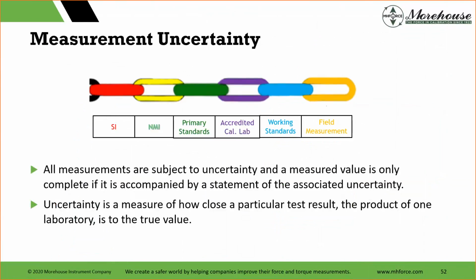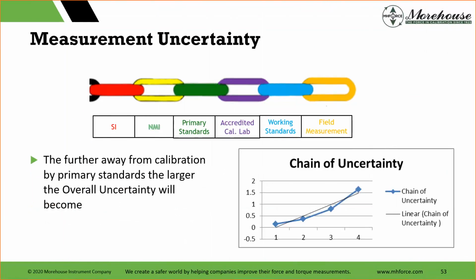Measurement uncertainty. All measurements are subject to uncertainty, and the measurement value is only complete if accompanied by a statement of associated uncertainty. Uncertainty is a measure of how close a particular test result, the product of one laboratory, is to the true value. Really what we're saying in that force graph in this one is, the further away calibration is from primary standards, the larger the overall uncertainty will become.